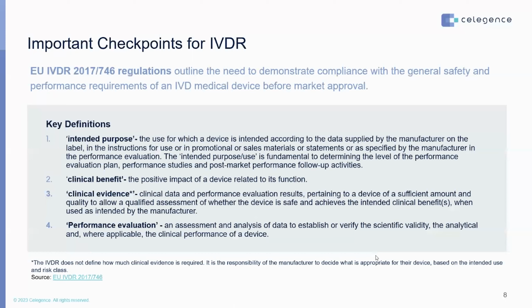This intended purpose is the basis for all of your performance evaluation. Your entire performance evaluation will be focused on showing that your device achieves its intended purpose. And by achieving its intended purpose, it has a clinical benefit. The clinical benefit here is a positive impact that the device has on the patient by nature of its intended purpose or its function. The clinical evidence here refers to any clinical data that you are using to demonstrate that the device achieves its intended purpose. And it is essential that this clinical data is of sufficient quality and amount to show that the device is safe when it's used as intended and it does have a clinical benefit associated with its use.